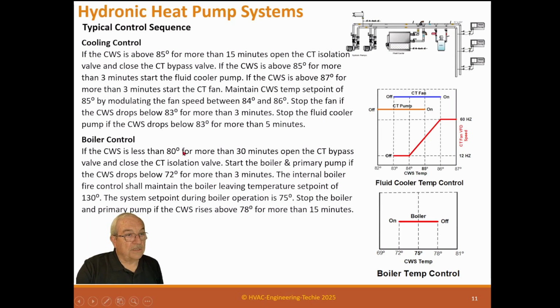So you realize that these set points are separated by these cooling set points, so we've got a dead band between heating and cooling. Up here in this cooling tower, we have this valve and this valve. This is an isolation valve, and this is a bypass valve. When we're in cooling, we shut this valve and force all the water through the cooling tower, and we open that valve. So this valve is open, this valve is closed, so all the water goes through the fluid cooler and out. During heating mode, we want this valve closed and this valve open, so all the water bypasses the cooling tower, so it's not letting the heat get out of it.